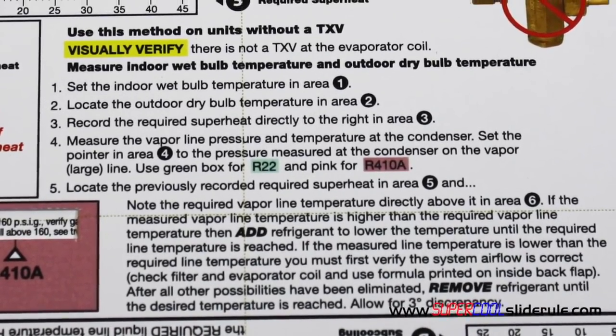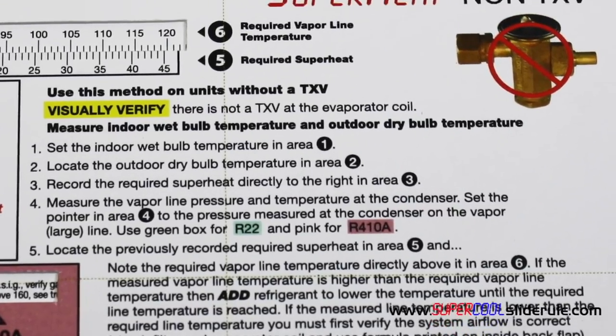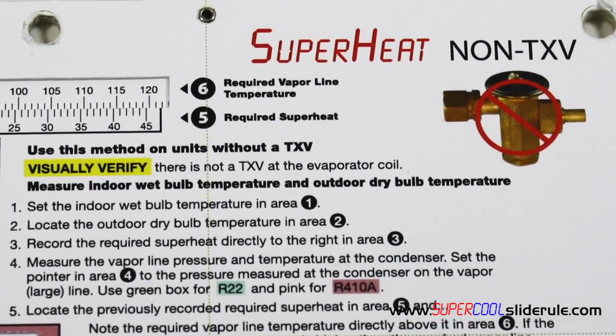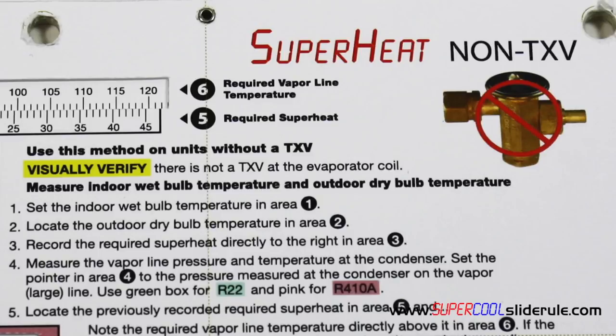Now before using this method, we must visually verify that there is not a TXV at the evaporator coil. This may require removal of the panel that covers the evap coil. Once we have visually verified that there is not a TXV installed, we can proceed with the process.